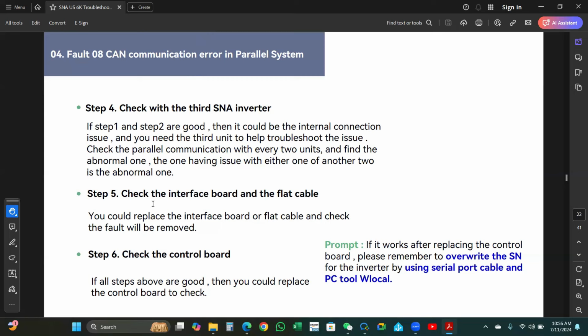Step 5, check the interface board and flat cable. You could replace the interface board or the flat cable and check if the fault is removed. Step 6, check the control board. If all the steps above are good, then you could replace the control board to check. Prompt: if it works after replacing the control board, please remember to override the SN for the inverter by using a serial port cable and PC tool Wlocal.